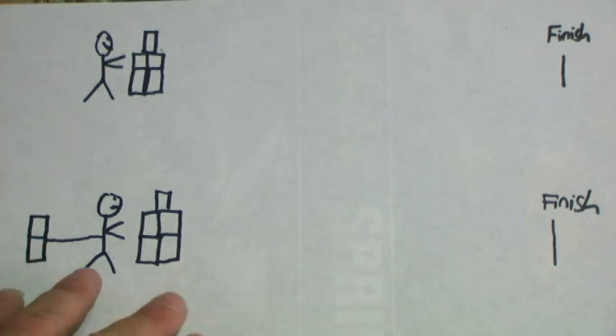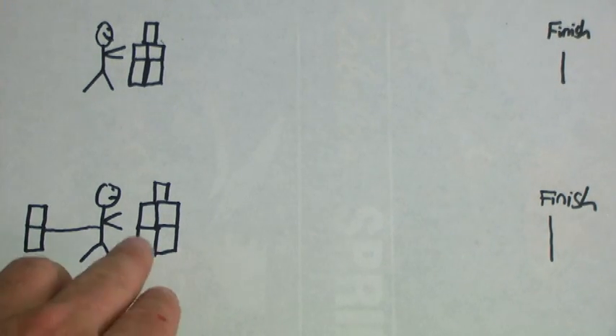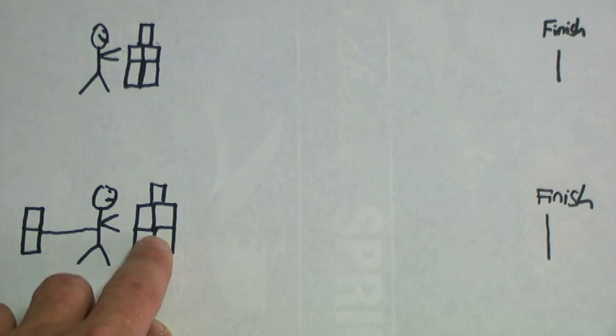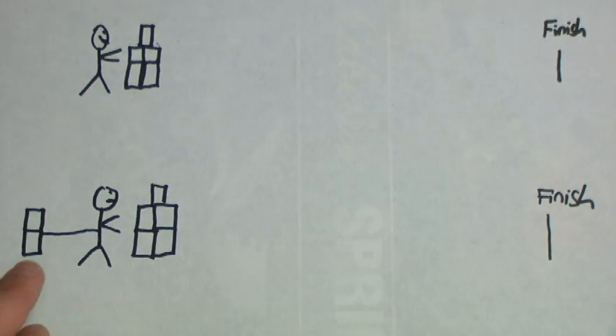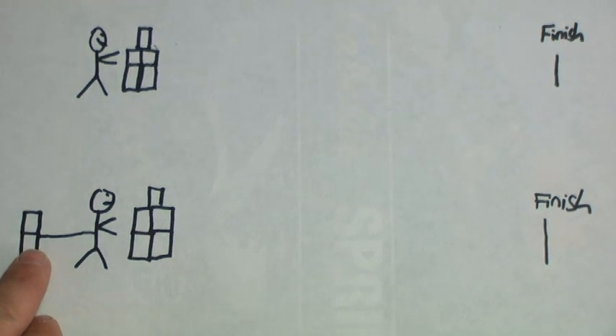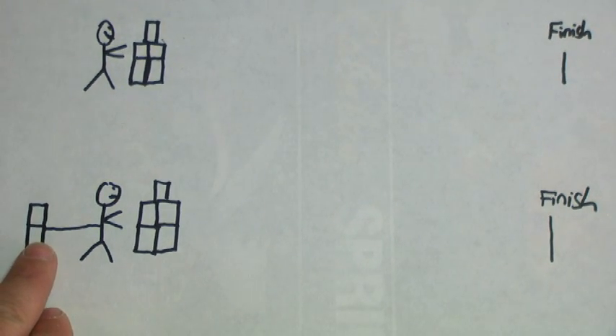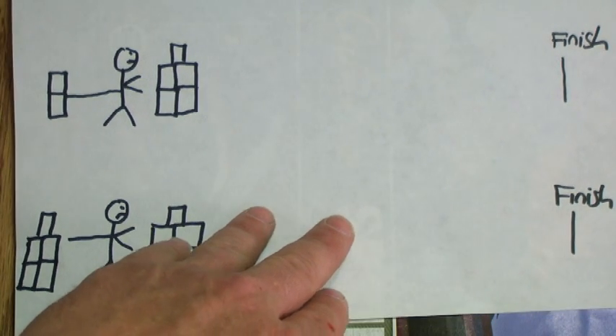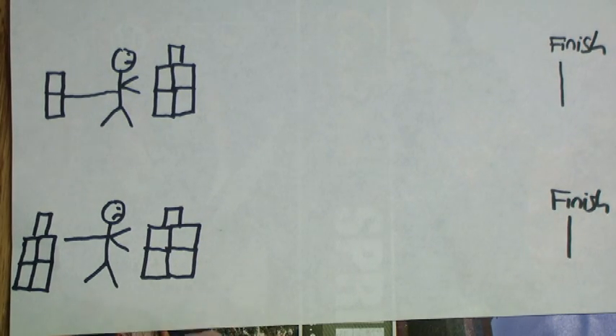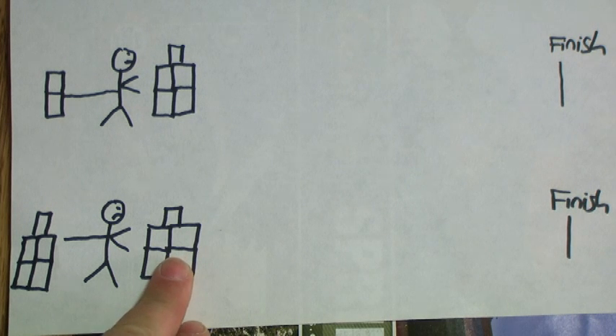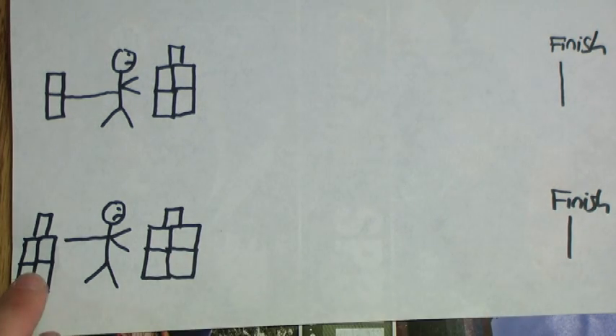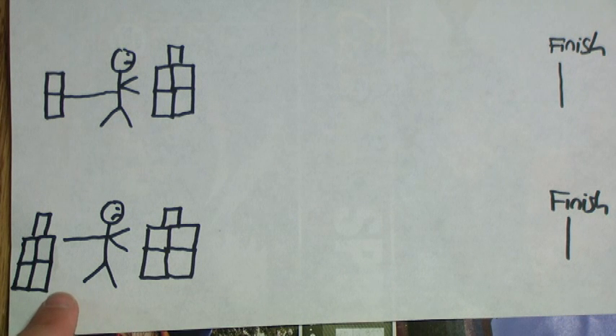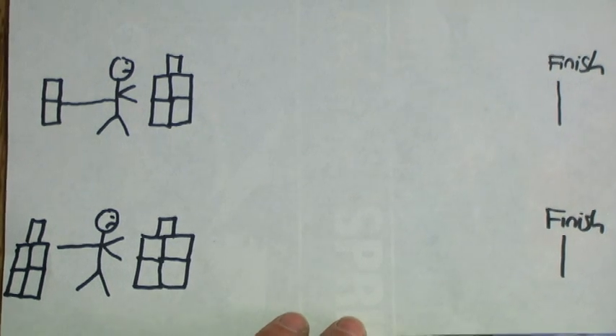Now if you measure your static pressure and it's a 0.7, I'm designed to push five. I'm going to push five, but I'm going to have two holding me back. That's going to make it harder for me to get my job done. Now if you've got the crazy static pressure, or one inch water column that's 1.0, we're still going to push half of that, five, but then we've got five that's pulling us too. He's going to do it, but he's going to struggle really hard.